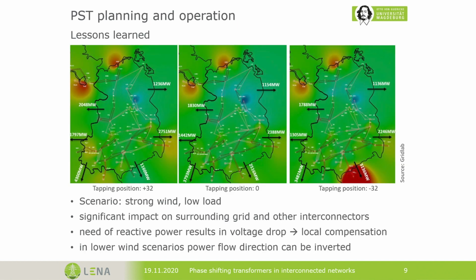This is a strong wind and low load scenario, which is considered to be sort of the worst case considering congestions and loop flows. And you can see that using this PST has a significant effect on all of the flows. Depending on the tap position, you can see in the left picture, we are blocking the flow. So from the voltage point of view, everything is fine. We redistribute the flow to all of the other interconnectors. In the middle, there is the neutral position. Now you can see that more than 1 gigawatt of flow could be blocked. And on the right-hand side, you can see the pushing position. So we are forcing flows through this interconnector to release flows on the other interconnectors, especially to Poland.